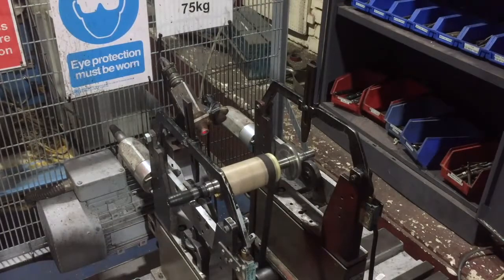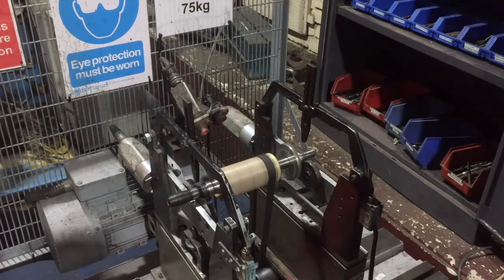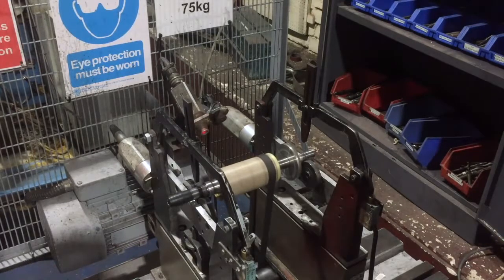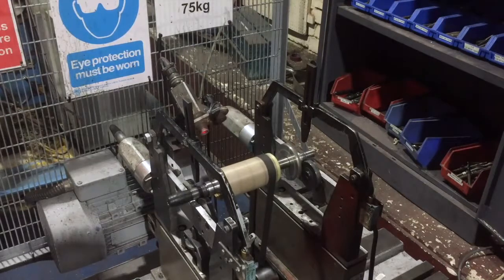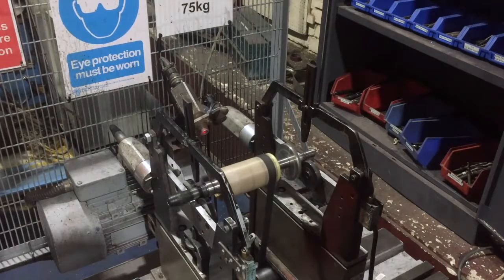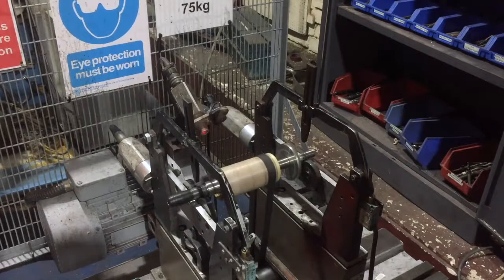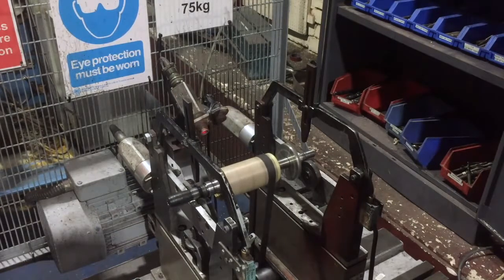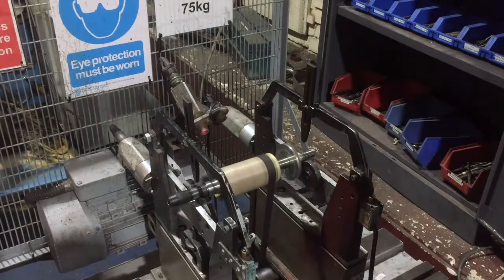This servomotor rotor is now on our balancing machine. Even though there was no report of any imbalance, we always like to check to make sure that we have got the right balance grade. And we always work to grade G 1.0. That is usually one balance grade higher than the manufacturer's standard balance grade. So here the machine is looking for imbalance in two planes, hence dual plane dynamic balancing.